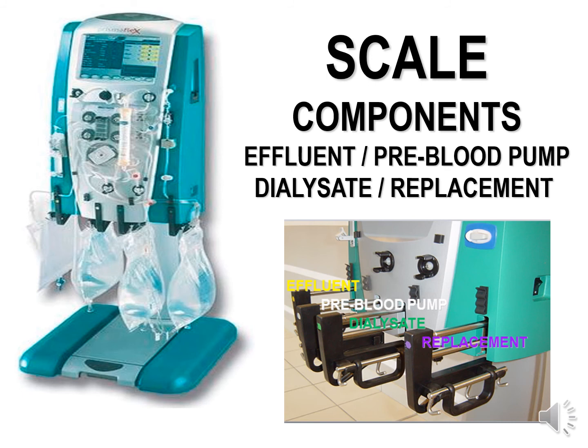When we look at the bottom of this machine, the scale components, you have the effluent, pre-blood pump, dialysate and replacement. So there are 4 scales that are constantly measuring the volume. And essentially what goes in should come out. So if you've got fluid, a litre goes in, then there should be a litre in the effluent.